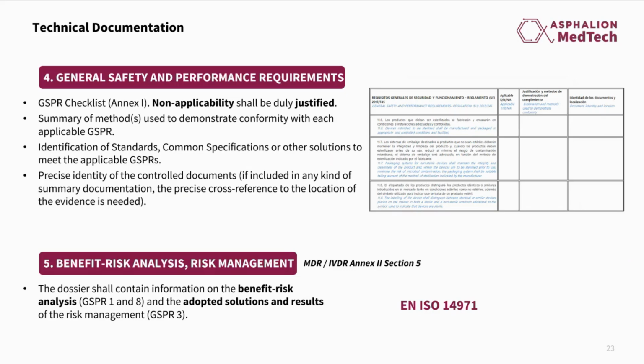Regarding module 4, this is regarding general safety and performance requirements. This module is typically drafted in a tabular format, as you can see in the slide, and you have to go one by one, requirement per requirement of the regulation, describing whether the requirement is applicable or not to your device. For example, imagine that you have a non-sterile device; therefore, requirements for a sterile device will not be applicable for you. And for those that are applicable, justify the methodology used to demonstrate compliance with that requirement, and also give a cross-reference to the documentation where you have explained how you comply with that requirement.